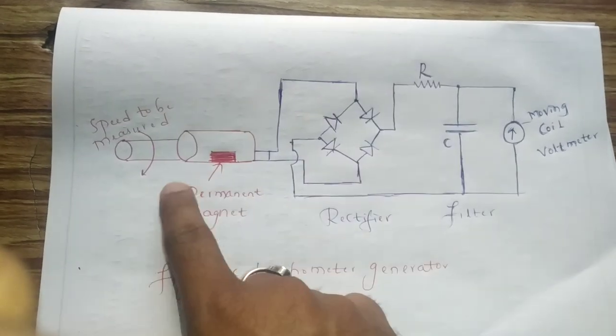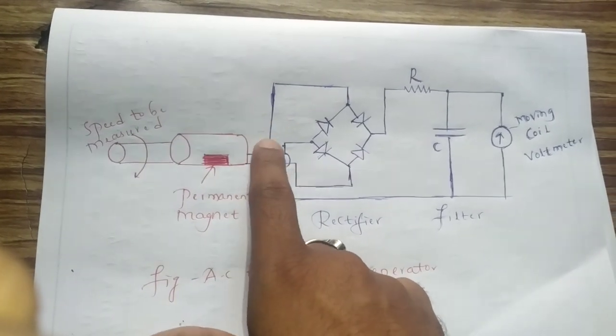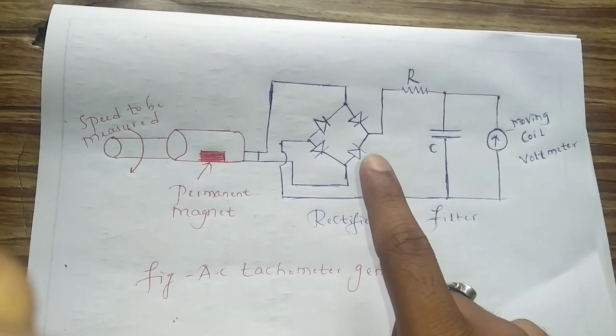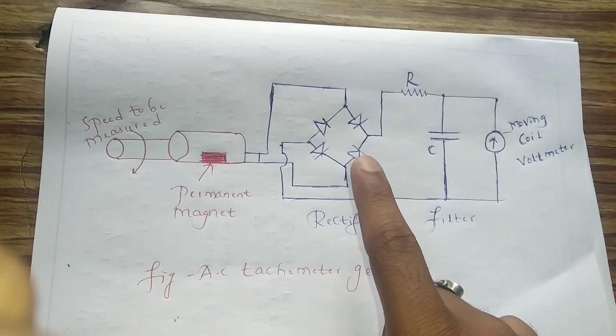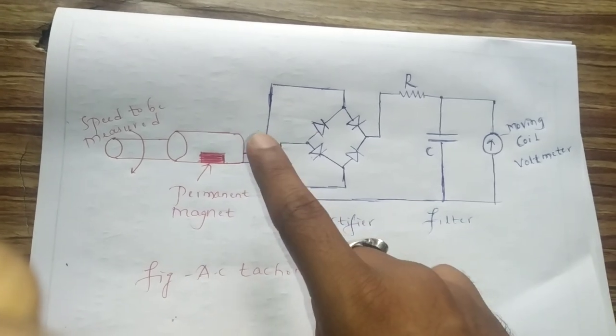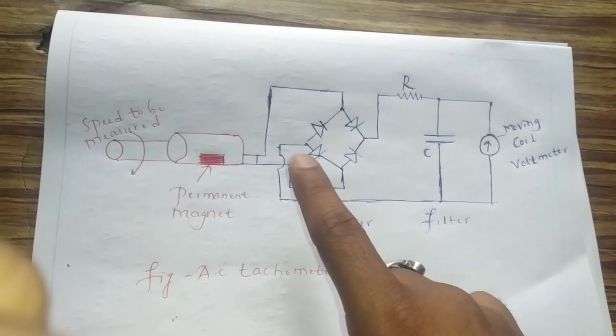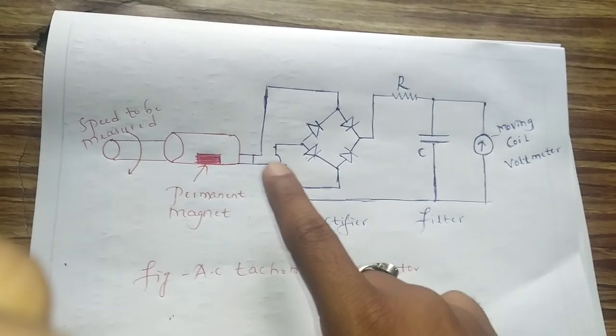The rotation of the magnet causes the EMF to be induced in the stator coil. The amplitude and the frequency of this EMF is proportional to the speed of the rotation. Thus either amplitude or frequency of the induced voltage can be used as a measure of rotation speed.